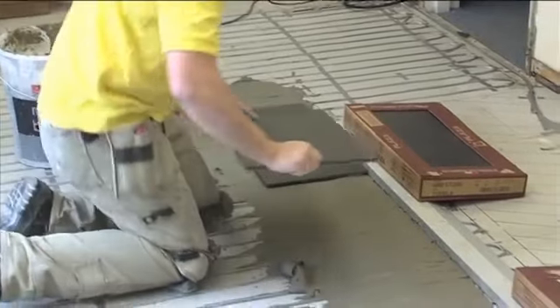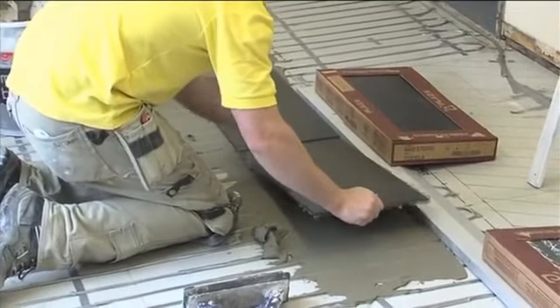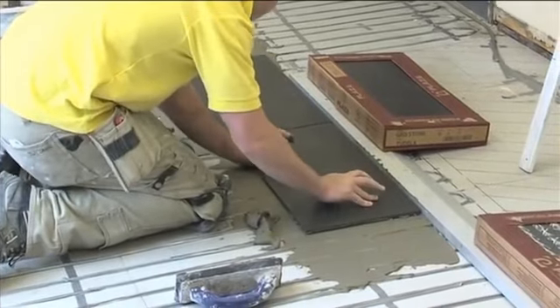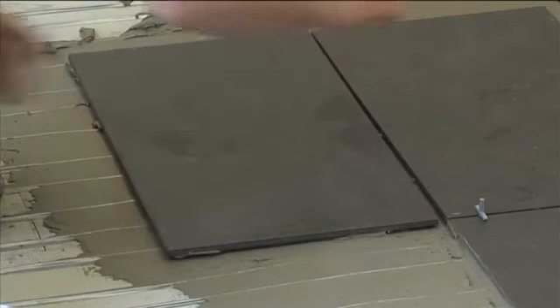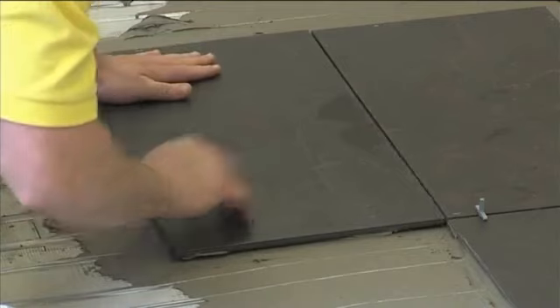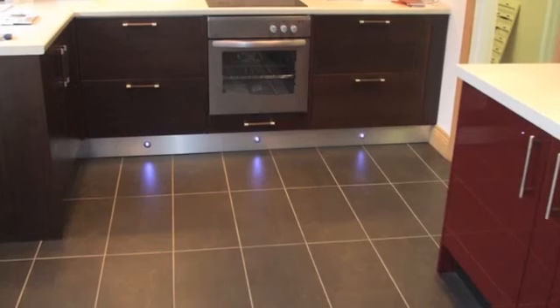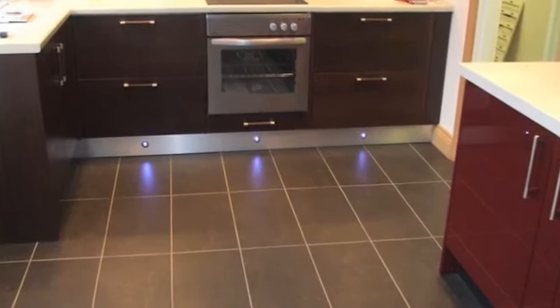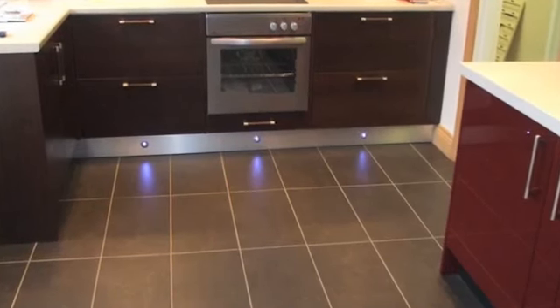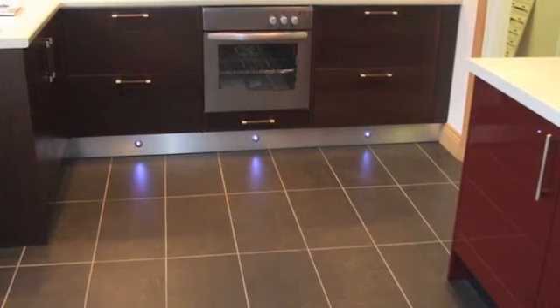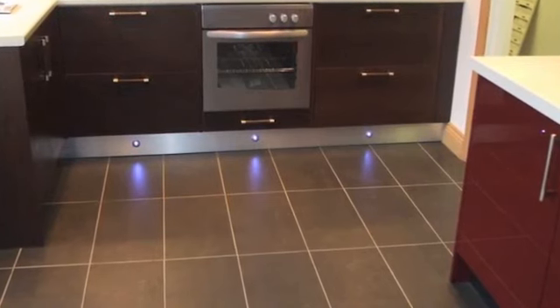Take care not to allow the trowel to come into contact with the heating cable when applying the adhesive. Use sufficient adhesive to ensure that no gaps or voids are left under the tile. The floor heating must not be turned on immediately after the tiling process. Consult the adhesive manufacturer for a suitable drying out period before turning on the heating system. This is usually around 2 weeks.